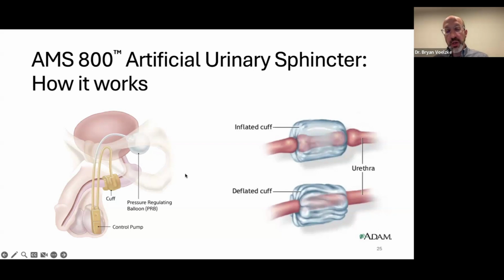With the artificial urinary sphincter, you can have a bladder that doesn't work, because the cuff is actually what's doing the work, as opposed to the sling, which is just supporting the urethra. The sphincter actually closes off the urethra, and then when it opens, the bladder empties. So if the patient's totally incontinent and they're able to empty, it's just by gravity. When they squeeze the control pump, the cuff will open, and they'll be able to empty their bladder. So we don't want people self-catheterizing through the cuff, and you don't want to have a catheter inserted in the urethra because that pressure of the catheter on the urethra can cause some damage.